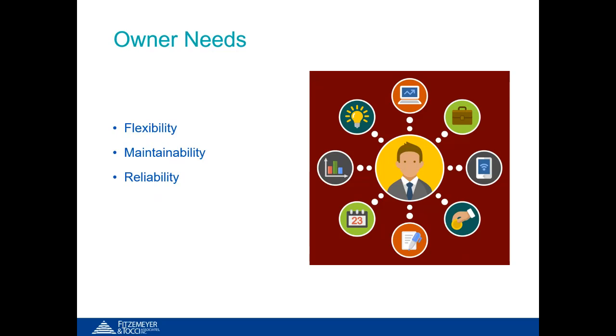Reliability is also critical. Redundant HVAC units can be provided to ensure that required air changes and pressurization are maintained during periods of maintenance or unit failure. This can be accomplished also through multiple fans and multiple cooling coils, or in the case of DX systems, refrigerant circuits can be used to ensure that temperature and humidity control can be maintained throughout the life of the project.